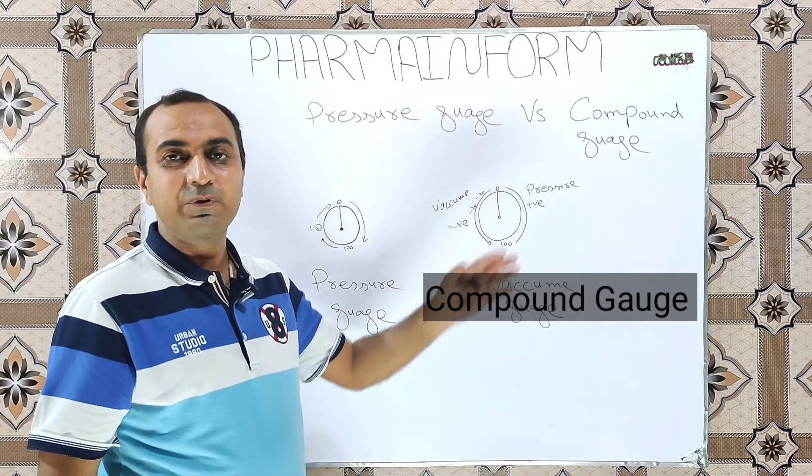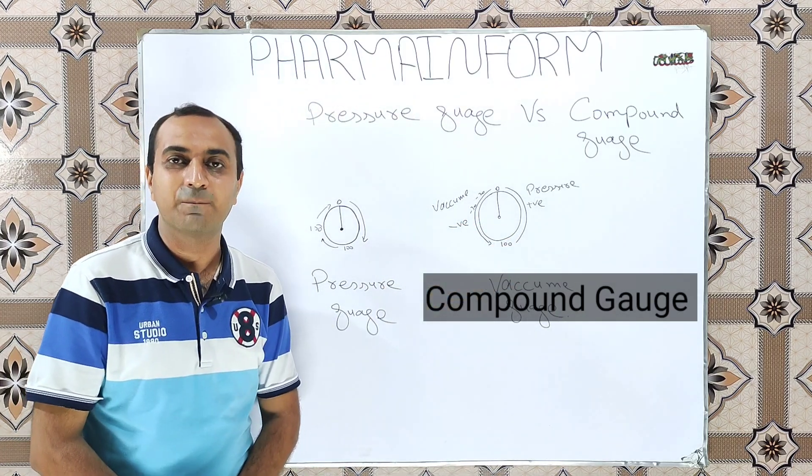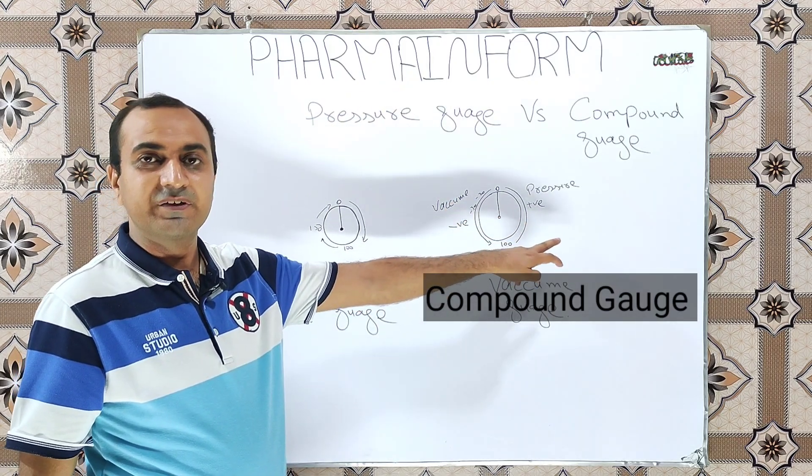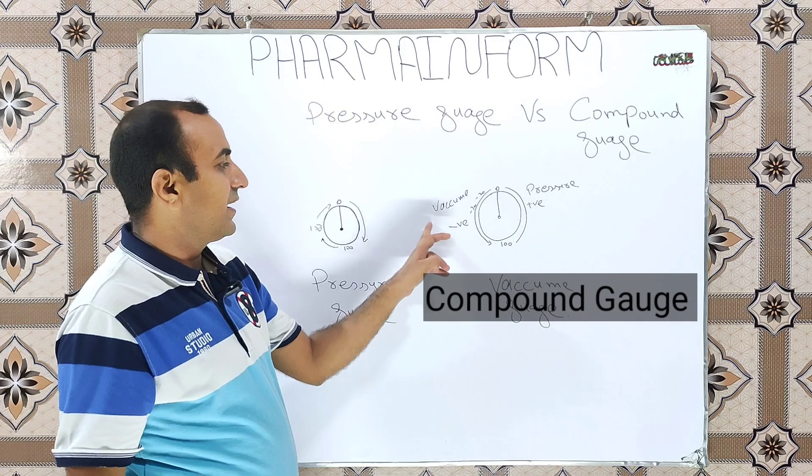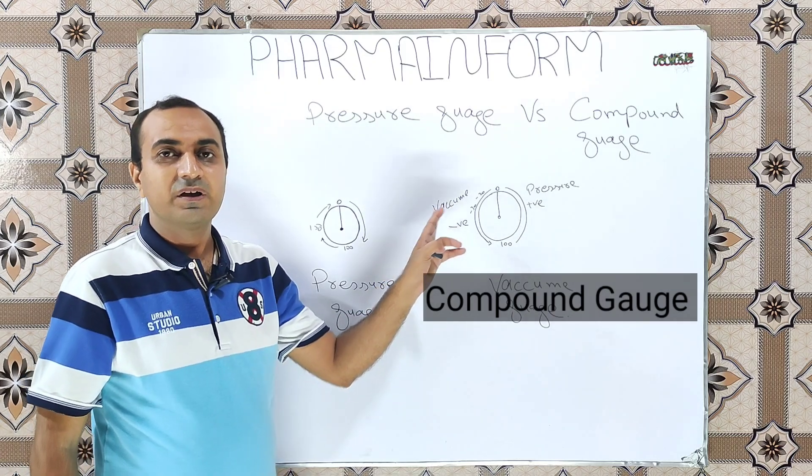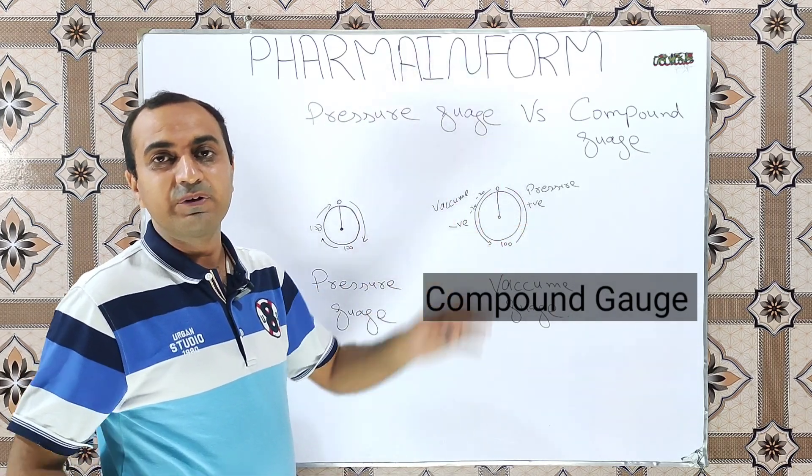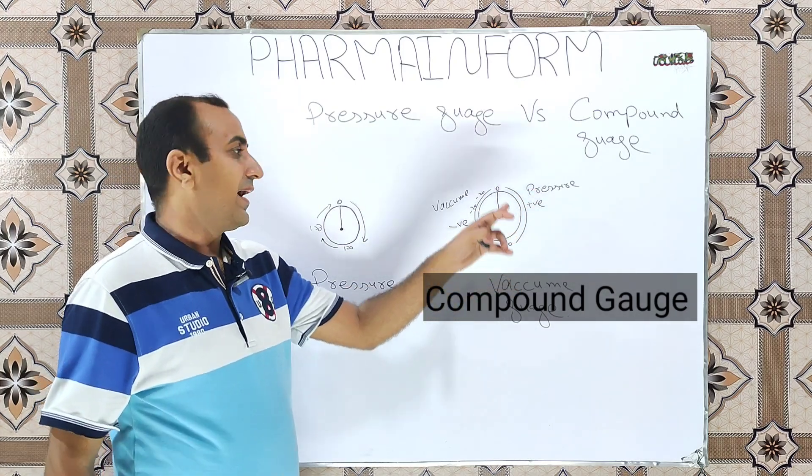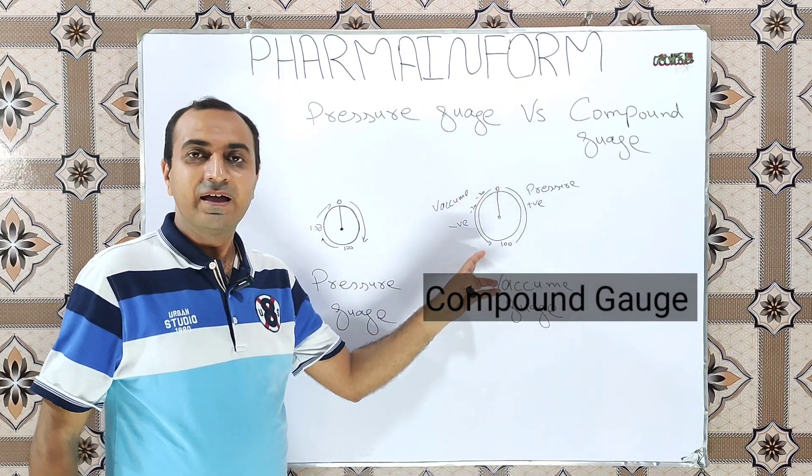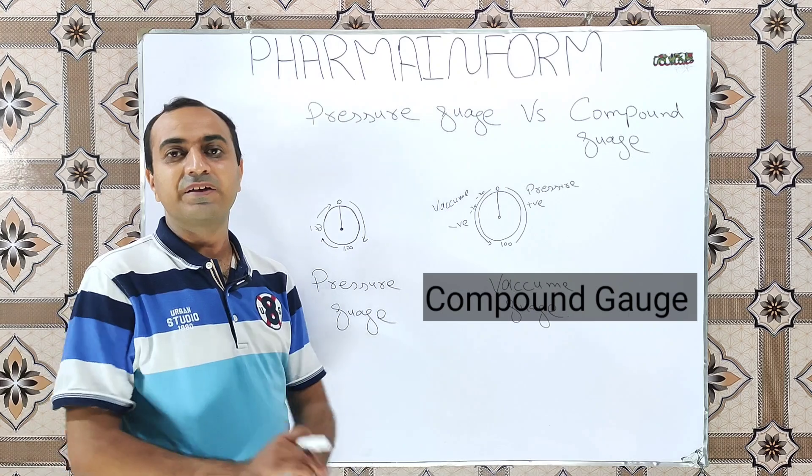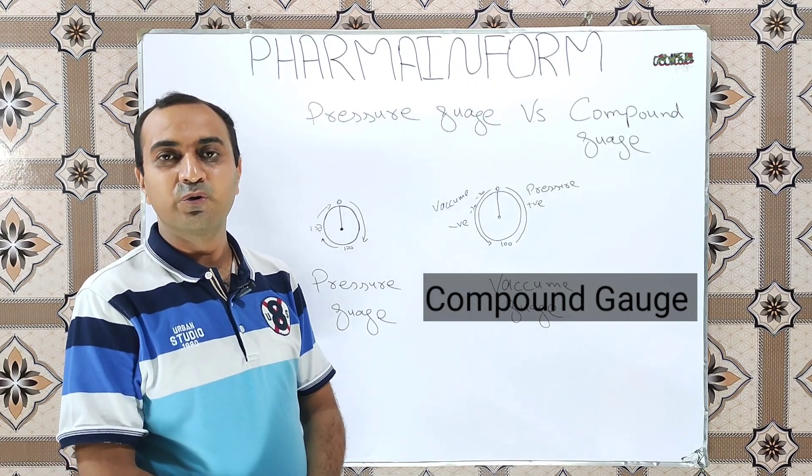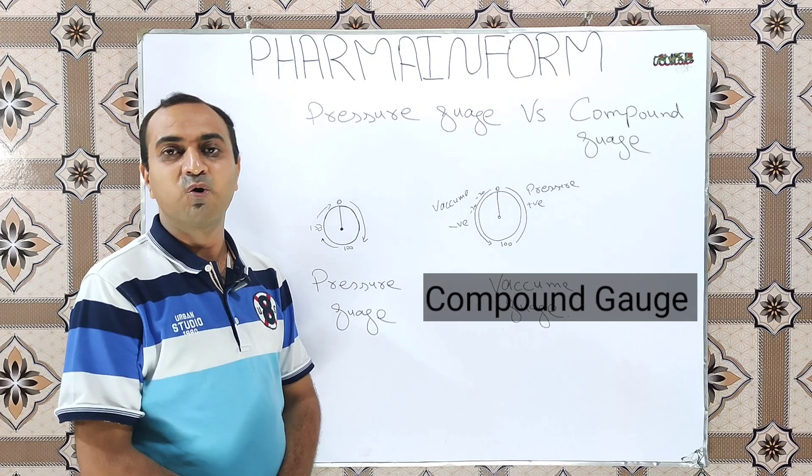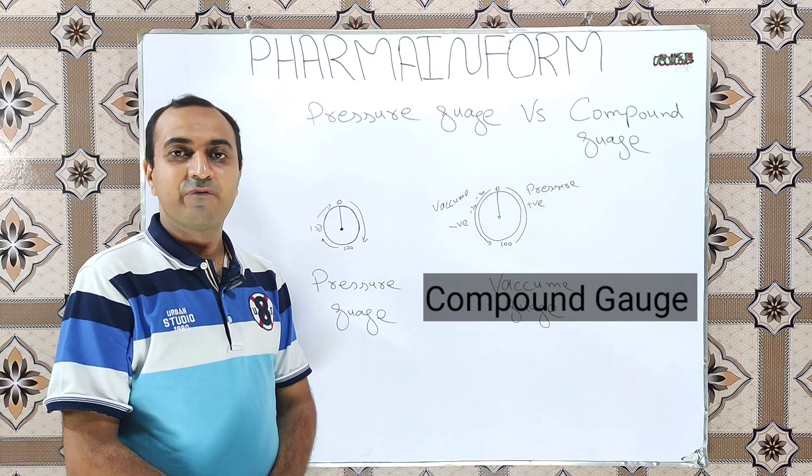So what is the purpose of compound gauge or what is the compound gauge? Compound gauge basically gives us two readings: one reading for the pressure and other reading for the vacuum. This gauge is marked with two values. One value is in positive digits and other value is in the negative digits. Compound gauges are installed on those equipments where we need to measure the value of both the pressure and vacuum.